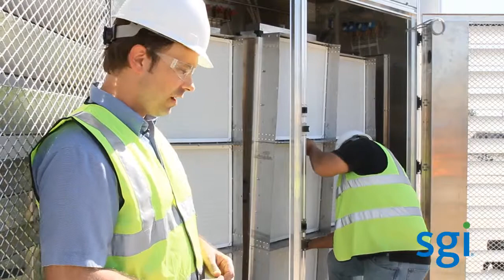We're able to provide 4 different sizes of evaporative media, and I'll talk about the filters shortly. Each evaporative section is a different size, which gives us the ability to modulate and control the rate of cooling inside the unit. So we're not just using a single blanket of evaporative media and running outside air through it. There's actually a lot of science into the size and what's inside the unit, which we'll talk about a bit - the size, shape, and type of evaporative media.